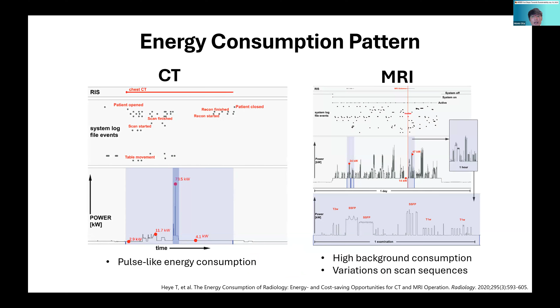It is estimated that approximately 2/3 of CT energy consumption occurs during idle time, and for MRI, even when turned off, about 1/3 of the energy is consumed. In other words, roughly half of the energy is used non-productively. Here are variations of imaging modalities in energy consumption. Reducing idle energy consumption by shutting down systems when not in use could lead to significant savings, although it depends on imaging modalities.